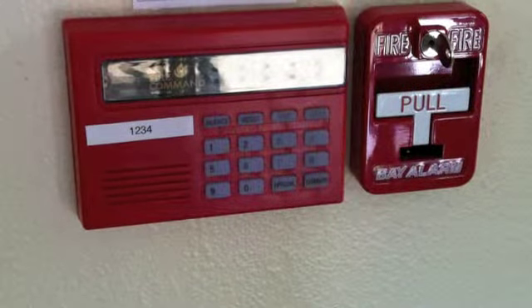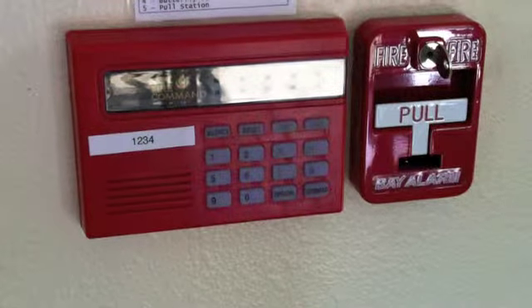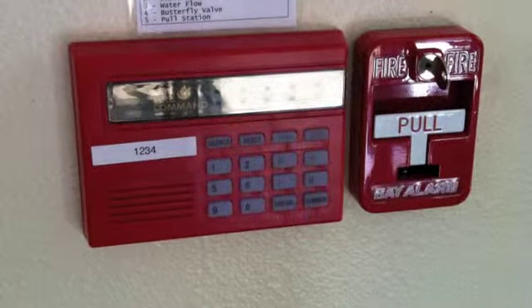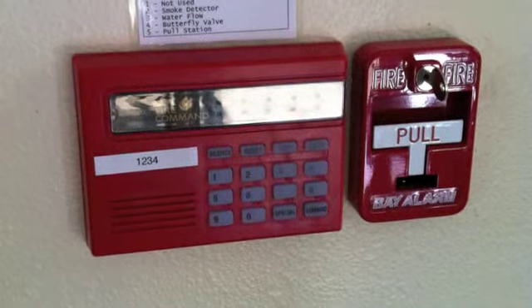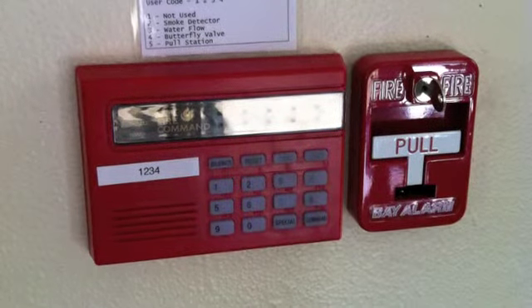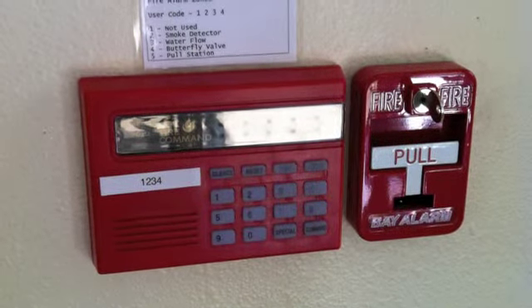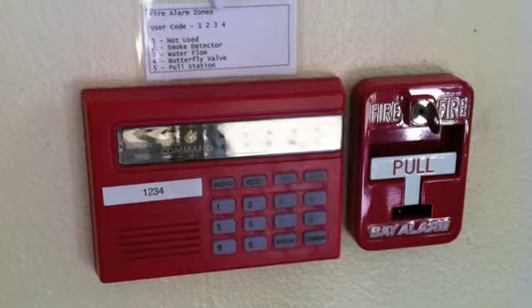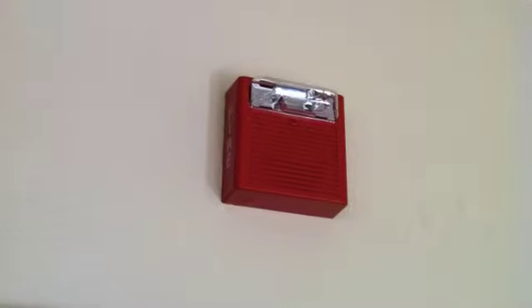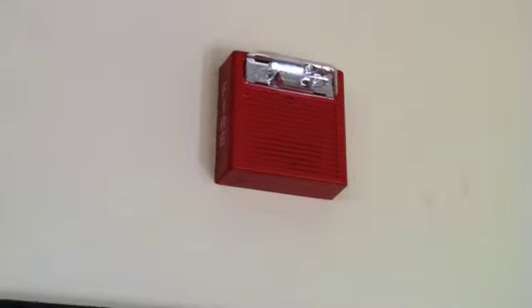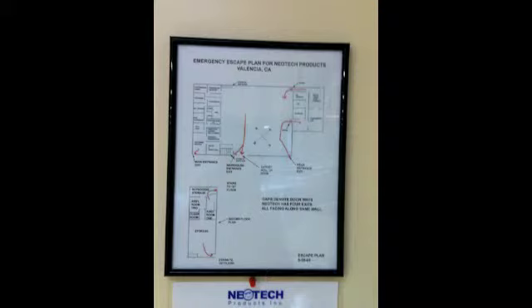Here we have the annunciator panel and the pull station. The annunciator panel will tell you what zone the fire is in, and you will be able to reset the sprinkler system after a fire. To the right is a pull station where you would pull the lever if a fire has occurred, which will sound these alarms. There are three main areas in the warehouse: the production area, the assembly room, and the offices.